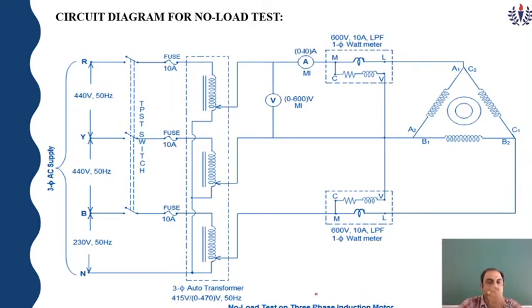Circuit diagram of no load test. This is the general circuit diagram of the no load test. Here we see R, Y, B and neutral. We are giving 3-phase 440 volt 50 Hz through the 3-phase auto transformer. The left hand side is the input and the right hand side is the output of the auto transformer. On the input side we are using a 10 ampere fuse. The output of the auto transformer will be connected to the wattmeters, both LPF, for the no load test.